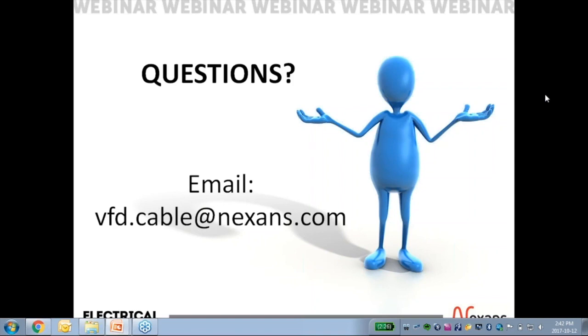Very good. Now getting to the actual construction of the VFD cables, Chris asks, can you explain the purpose of having the three ground wires again? So the three bare bond conductors, each placed between pairs of phase conductors, it gets rather technical, and this is where the drive manufacturers have a wealth of documentation on the technical reasons, and it really comes down to common mode currents. Basically, this idea that if you take all three phase conductor voltages and add them up in a typical building wire sinusoidal output three-phase system, you'll get precisely 0 volts.